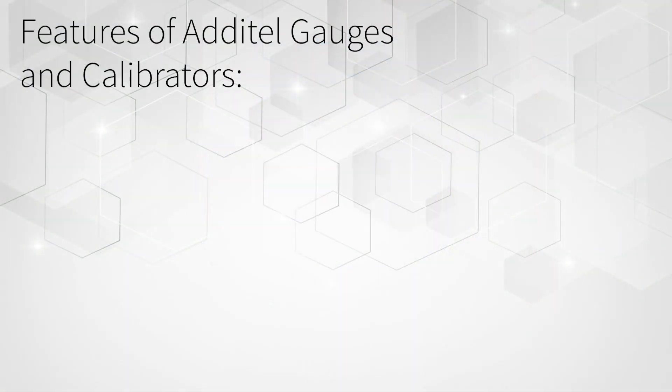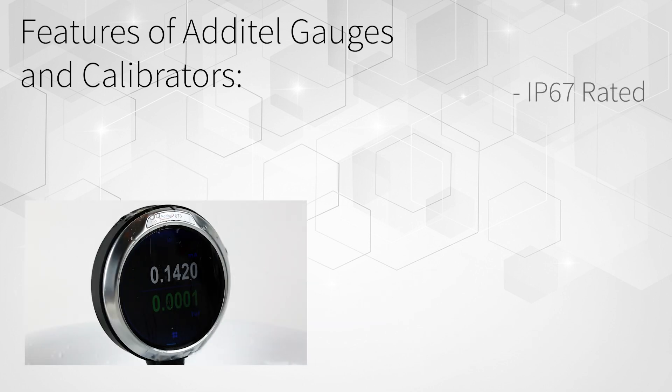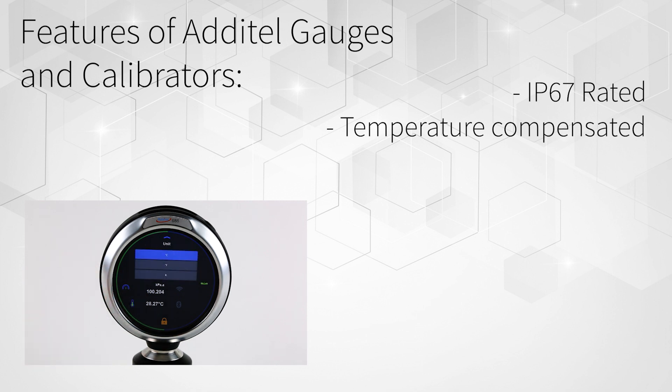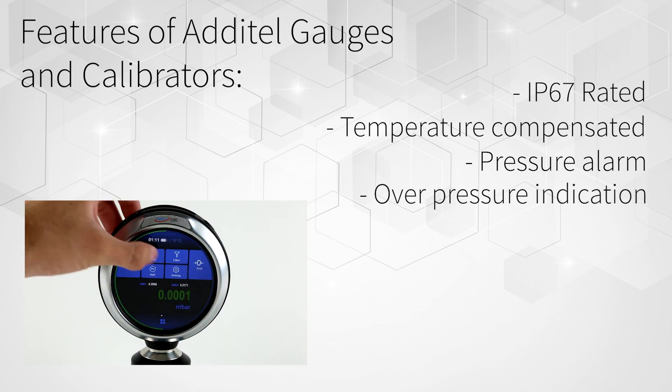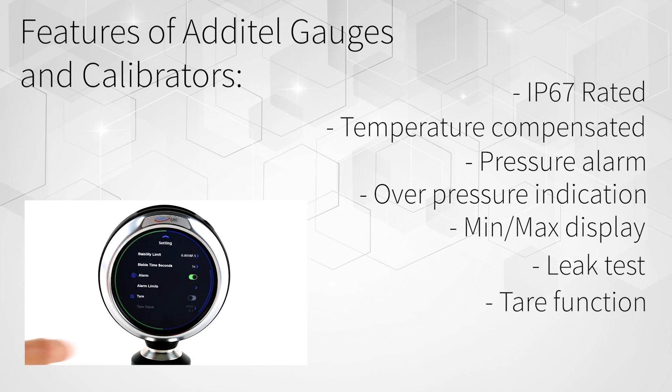The following are other features included in all three of these highly capable Additel gauges and calibrators. All gauges are IP67 rated, have fully compensated pressure accuracy over the temperature range of 0 to 50 degrees Celsius, have user programmable pressure alarms, overpressure warning, a minimum and maximum pressure display, leak test, tare function, and snapshot.